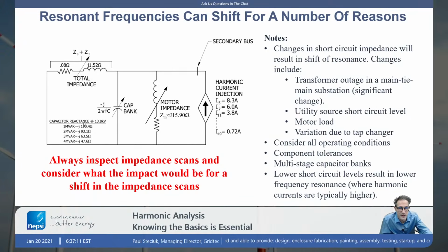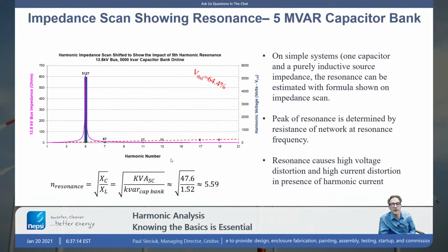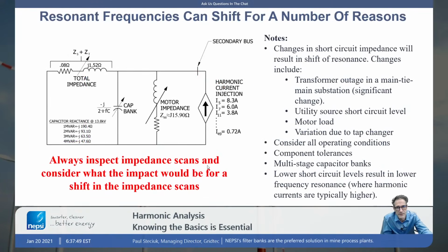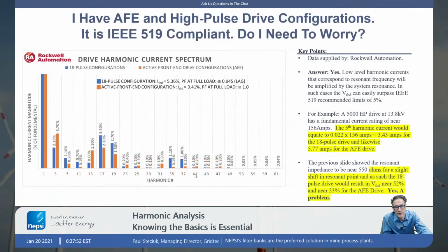So when you do harmonic analysis, you can't just look at the values of voltage and current distortion. You have to take a look at the impedance curves and say, okay, let me do a perturbation on the system. Let me make some changes here. What changes are reasonable, and can I have a resonance concern? Can I have a resonance issue? This is something you have to look at. So that's the importance of the impedance curve, to look at that curve and say, if I shift left or right, can I run into a resonant condition? Can it overlap one of my dominant harmonics in the network? And so always consider that possibility.